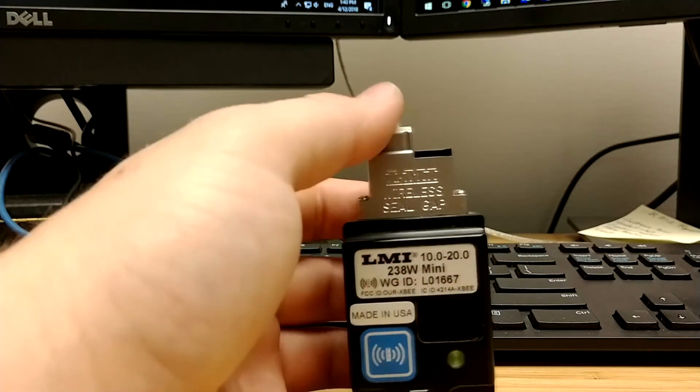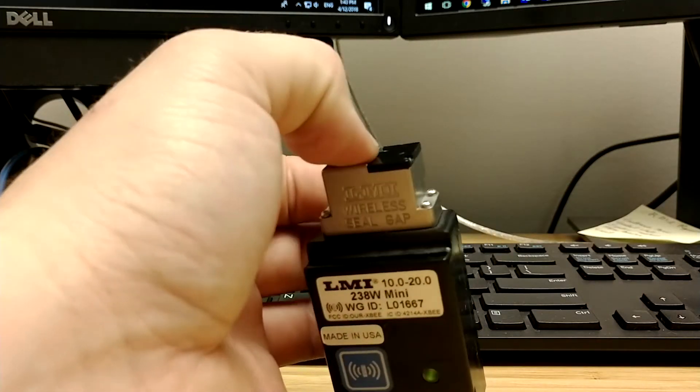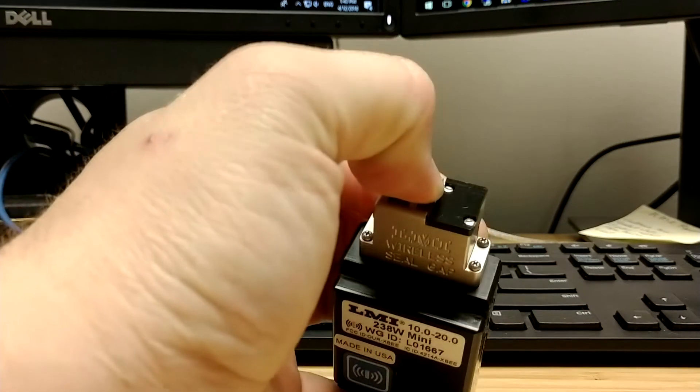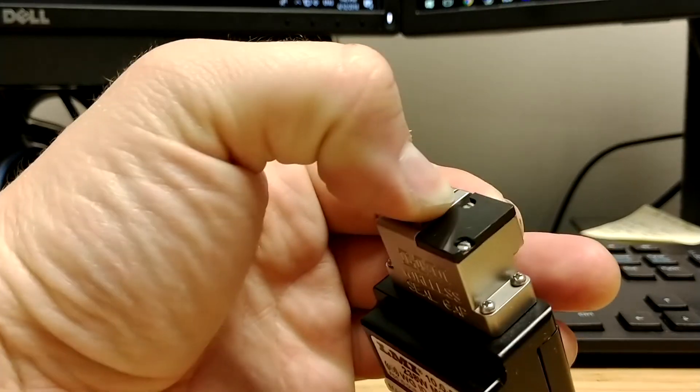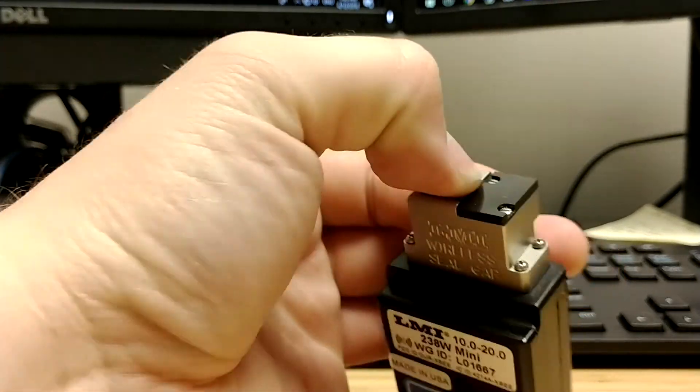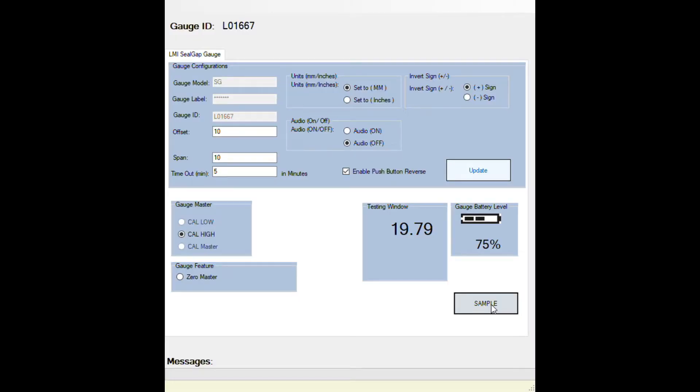For cal high, completely compress the gauge and use your fingertip as the plunger goes below flush. Click on sample again.